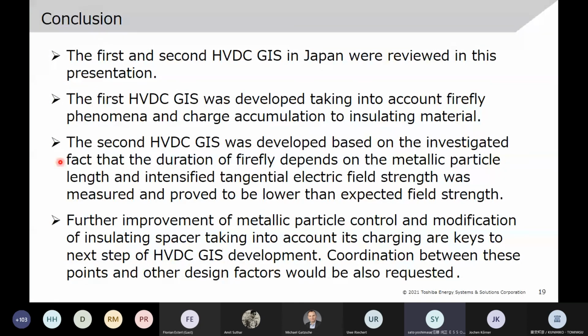The second HVDC GIS was developed based on the investigated fact that the duration of firefly depends on the metallic particle length, and the intensified tangential electric field strength was measured and proved to be lower than expected. Finally, I suggested that further improvement of metallic particle control and modification of the insulating spacer, taking into account its charging, are keys to the next step of HVDC GIS development.